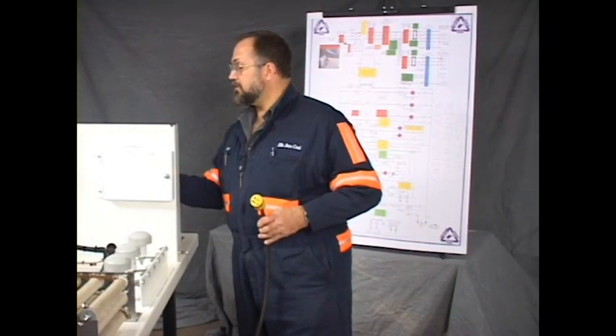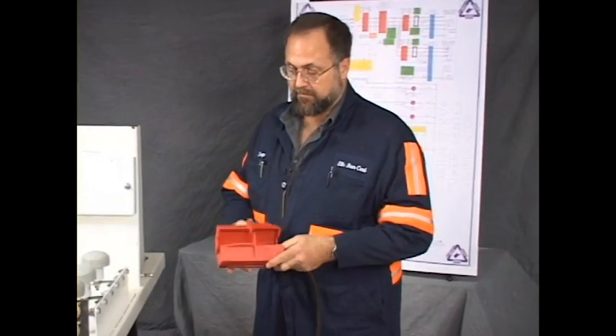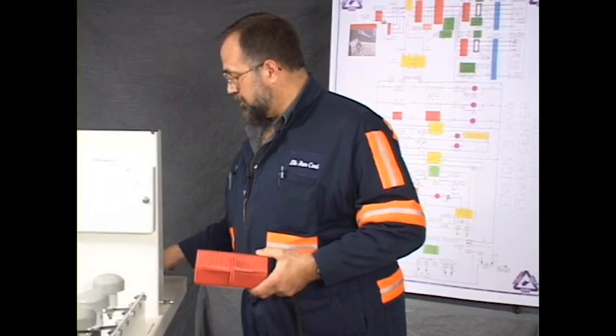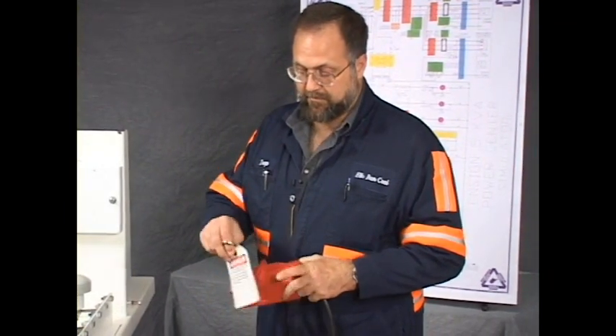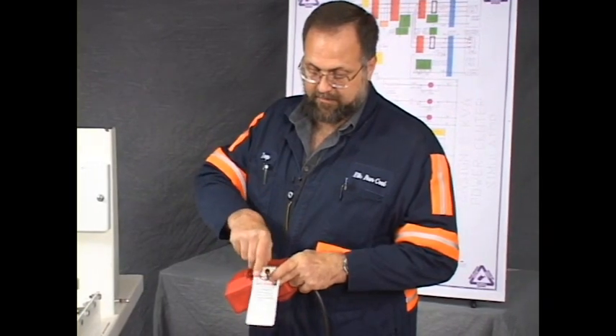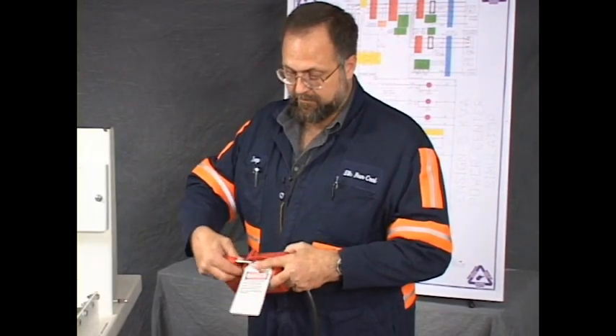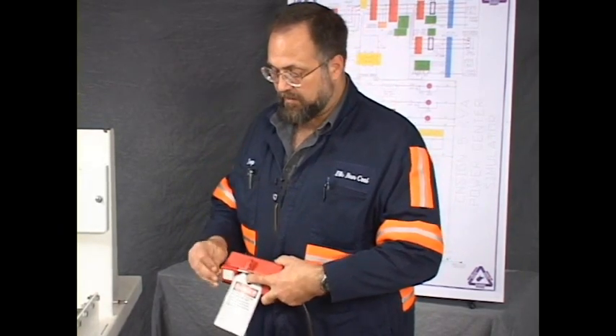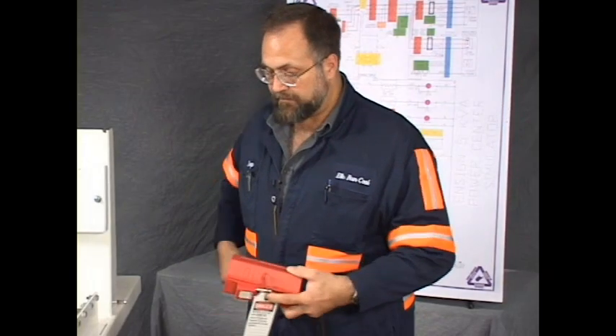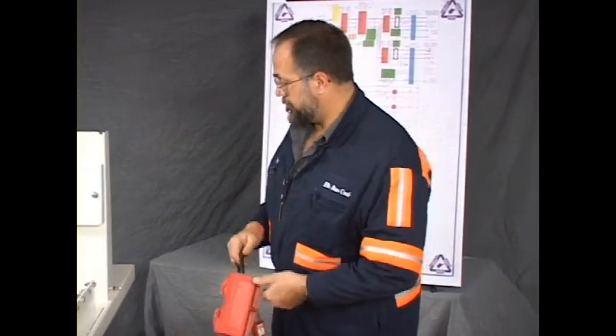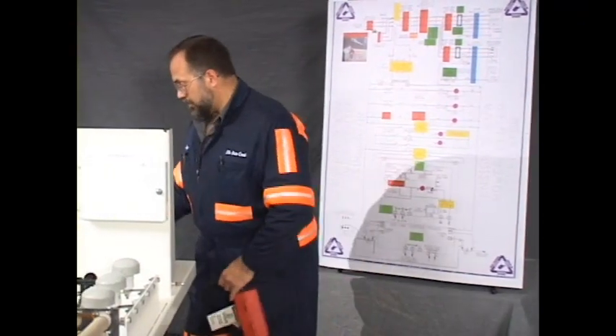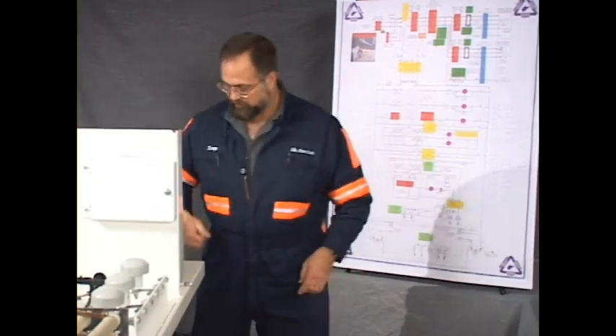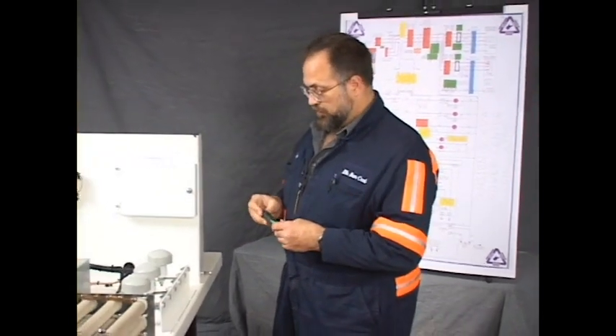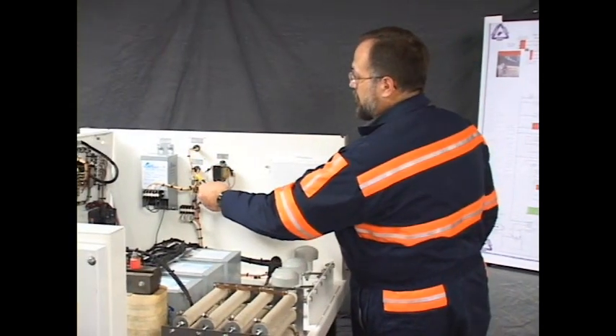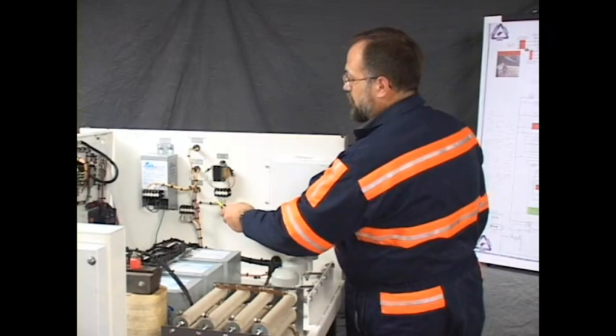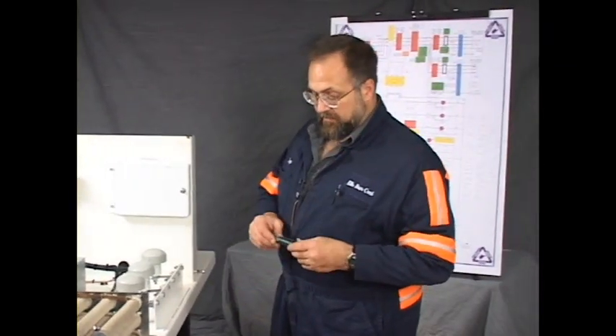And prior to troubleshooting, we're going to make this cord safe by disconnecting, visible disconnect, and installing a danger tag and a lock. And after the cord is locked out, you take the key away, keep the key with you. Even though we've locked it out and disconnected it from the source, we're going to take a moment to make sure that we have no power with a voltage detector. As you can see, the voltage is absent. There's no voltage found anywhere in the box. That's an important and necessary part.